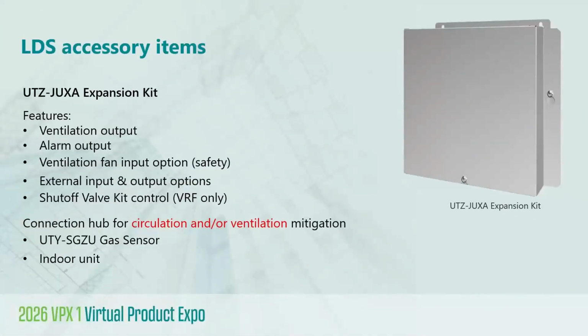So before discussing how the expansion kit can address the cable length limitations I just mentioned, let's talk about the kit itself. In simple terms, from an installation and wiring standpoint, you could say that the expansion kit acts as a connection hub that manages the inputs and outputs required when the next level of mitigation is required, which is ventilation. So unlike circulation, ventilation will activate a third-party fan or ERV or HRV or some other device to introduce outdoor air or air from another space to dilute the refrigerant in the space if that concentration threshold is exceeded. So again, ventilation helps dilute by introduction of additional air. It's important to note that whenever the expansion kit is used, you're going to need the gas sensor also, again, except for units that have the factory installed LDS. So that's important to know.